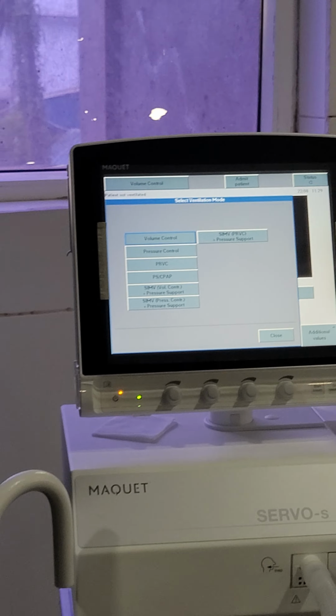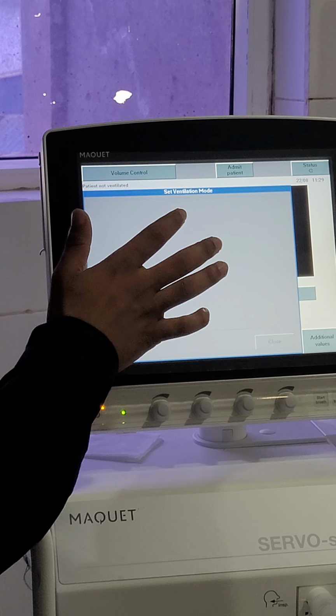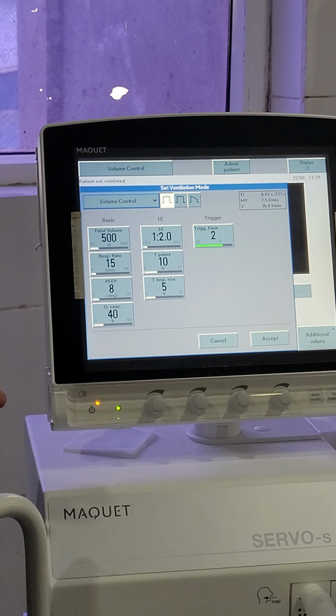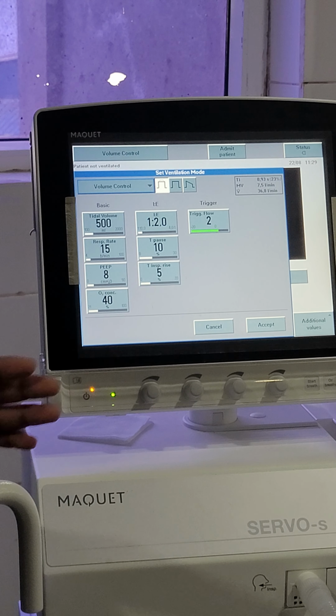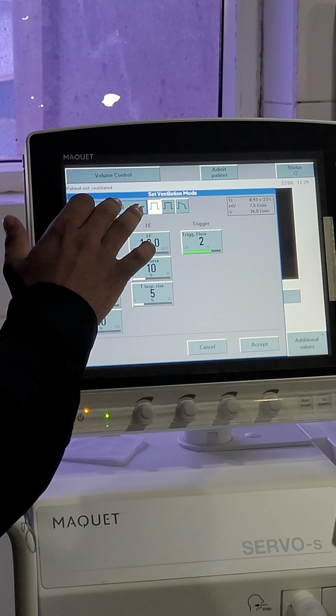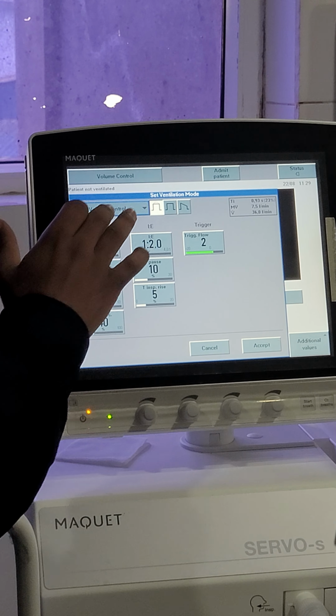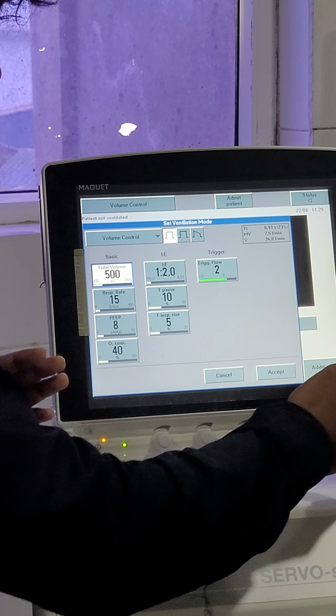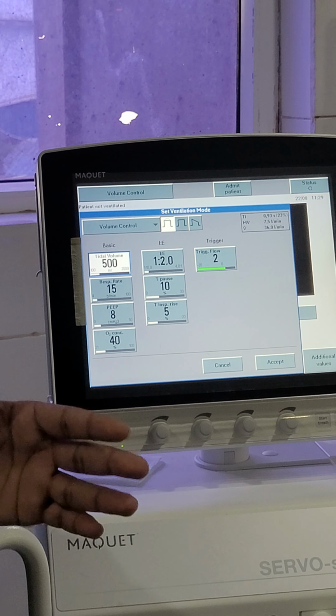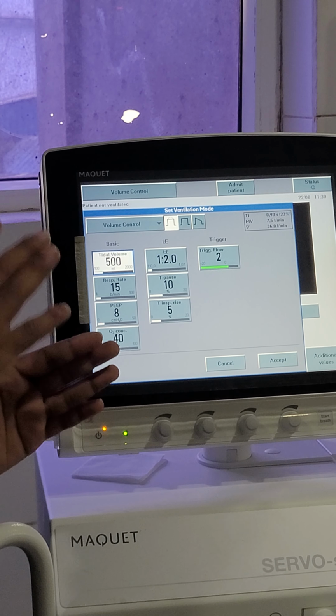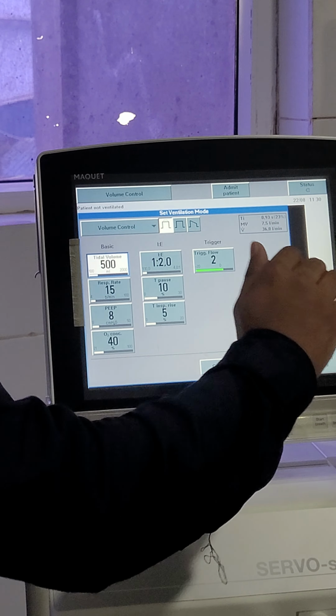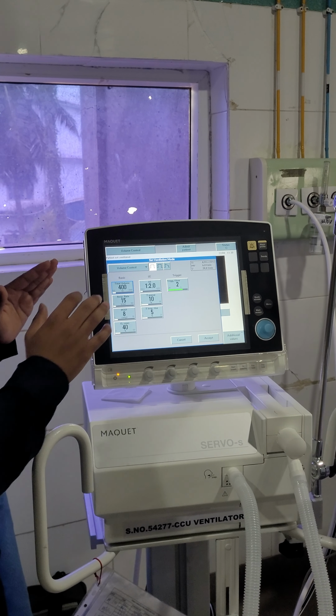You want me to explain about the modes? Volume control is a mode where volumes are constant, pressure will vary based on the lung dynamics of the patient. If I want to go for volume control, I will be pressing volume control, tidal volume. To set the parameters, I will be pressing on the parameters I want to set. Again, it is based on the ideal body weight. I am not going to talk in detail. I will just tell how to set it. If I want to increase it, clockwise; if I want to reduce it, anti-clockwise. 400 tidal volume I am setting.